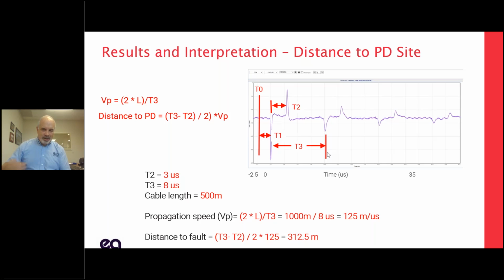This doesn't happen all the time with online testing because we have noise floors, we have things connected, so we don't get great reflections. Offline you can do this, but occasionally online we can do it. So probably about 20% of the time we can actually do an online test and determine the distance to PD.